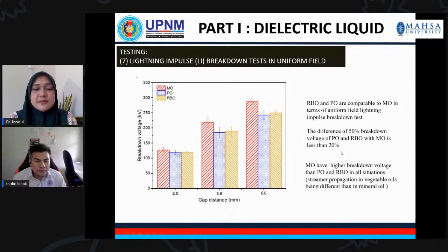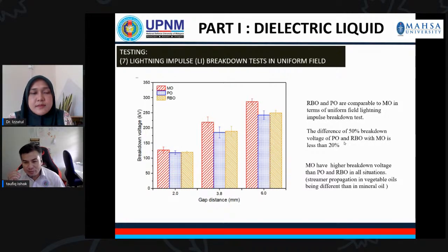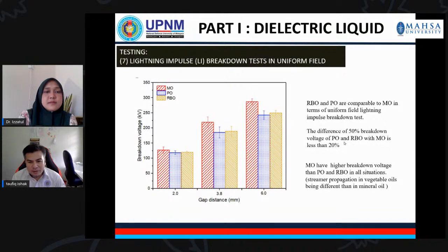The difference of the 50% breakdown voltage, which is the average breakdown voltage, of palm oil and vegetable oil compared with the mineral oil is less than 20%, which is reasonable in terms of transformer design. When we did the streamer study, we understood why the vegetable oil has lower breakdown voltage: the streamer propagation in the vegetable oil is faster than inside the mineral oil. Meaning that the electrons move faster inside the vegetable oil as compared to mineral oil, and hence it can reduce the breakdown voltage of that particular oil. That's why, as you can see from the result, mineral oil has higher breakdown voltage as compared to vegetable oil.